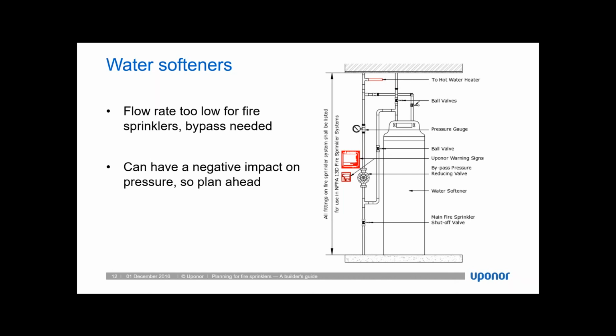Now, the way that this pressure-reducing valve works as a bypass is that it is set to only allow water through at a pressure that is slightly higher than what the system demand will be at that point in the event of sprinkler operation. The goal is that through day-to-day operation, the water pressure on the system side of the softener and the pressure-reducing valve is higher than the set pressure of the valve. In that case, the water itself acts as a barrier to allowing water to flow through that pressure-reducing valve.